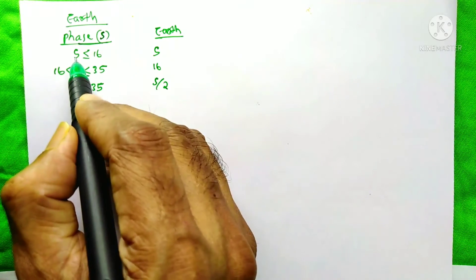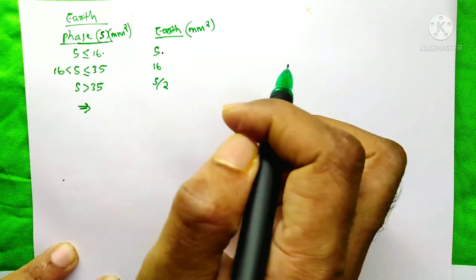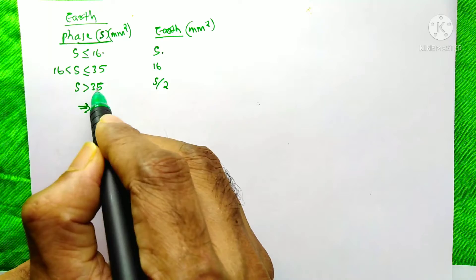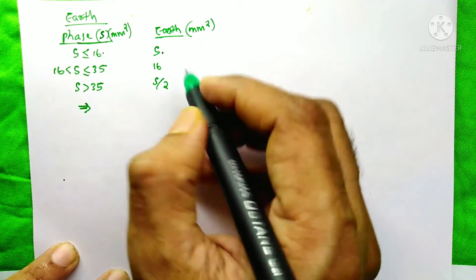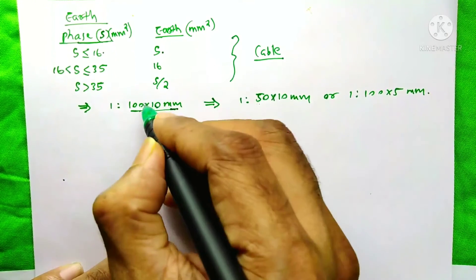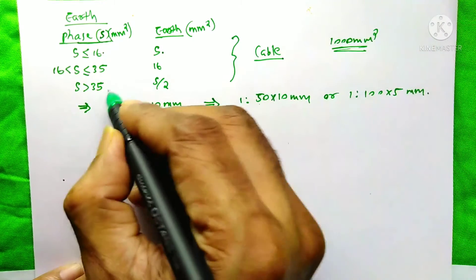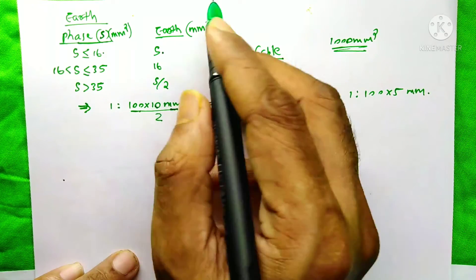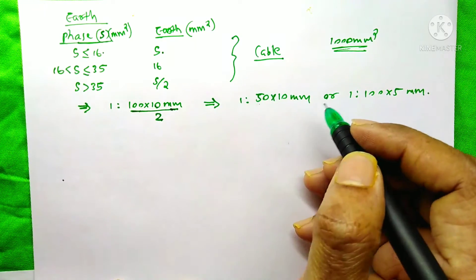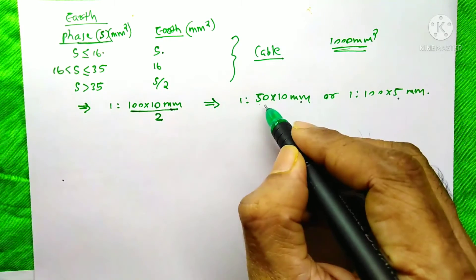Next, sizing the earth bus bar. If the phase bus bar area ≤16 mm², earth = same as phase. If >16 mm² and ≤35 mm², earth = 16 mm². If >35 mm², earth = half of phase. Our phase conductor is 100×10 = 1000 mm², which is greater than 35 mm², so earth = half: 100×10 / 2, giving options of 50×10 mm or 100×5 mm. I prefer 50×10 mm.